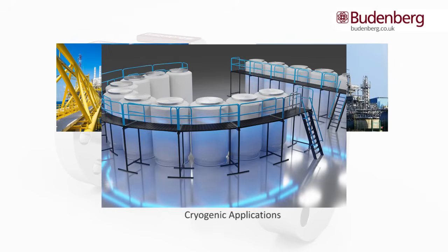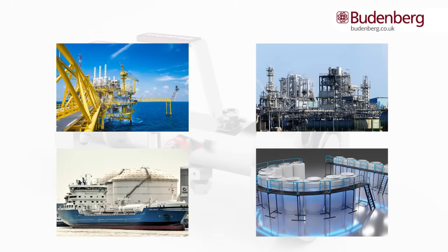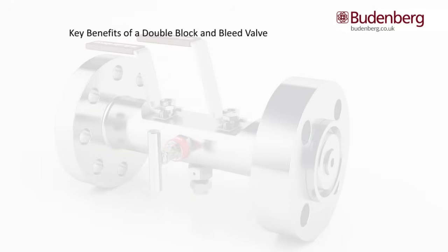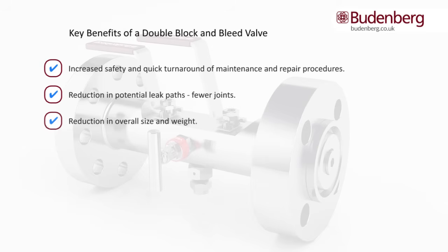They are also used in cryogenic applications, storage, and transmission industries, and could be utilized for both chemical injection into the process or sampling of the process. By strategically incorporating double block and bleed valves into a process system, you are increasing system safety and integrity by having an additional isolation as a fail-safe. This also leads to a quick turnaround of maintenance and repair procedures. A reduction in potential leak paths is also an advantage, as there are fewer joints, and the overall size and weight can also be reduced.